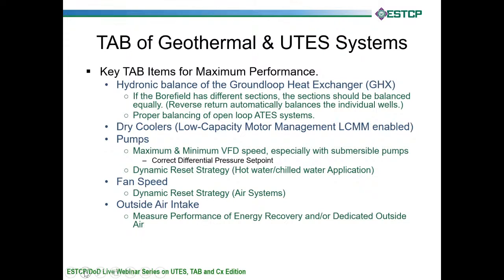We'll talk about dynamic reset strategy for pumps, how we're going to dynamically reset the pump differential pressure set point. That's for hot or chill water application, or even loop water application. And then fan speed would be the same thing. The tab contractor can help dynamically reset or implement a dynamic reset strategy for the air systems, which would reset the static pressure set point for the fan to meet the load of the building, to keep the fans from running too fast. We don't want them to run any faster than they have to.